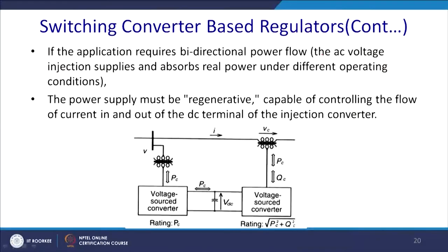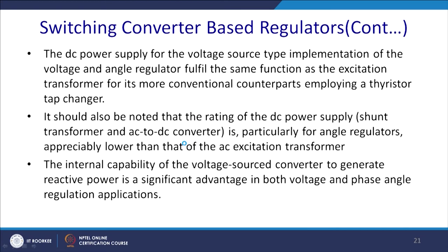bidirectional power flow, where the AC voltage injection supplies or absorbs the real power under different operating conditions, then the power supply should be regenerative, capable of controlling the flow of current into and out of the DC terminal of the injection converter. So power has to be bidirectional. In this case, we have to change some topological aspect. So what happened? The DC power supply for the voltage source type implementation of the voltage and angle regulator fulfills the same function as the excitation transformer for its more conventional counterparts employing a thyristor tap changer.